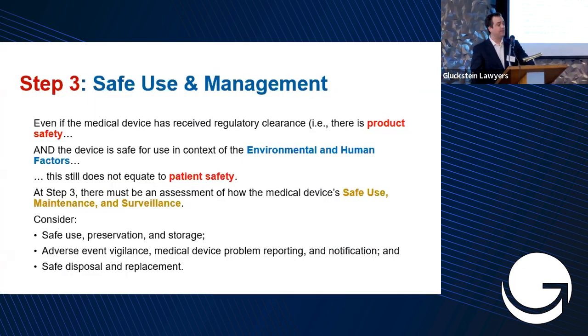And step three, safe use and management. So manufacturers are required to provide a number of things in the context of providing medical devices to the community. They are required to provide instructions for safe use, to preserve and maintain the quality of the device in the delivery process to the customer, and to conduct post-market surveillance, adverse event reporting, corrective action, and preventative action. After delivery, however, the device is possessed by the user, and it's the user of the device, and that may include the patient who's using the device, whose responsibility is to follow the safe instructions, maintain device quality, and monitor device performance.